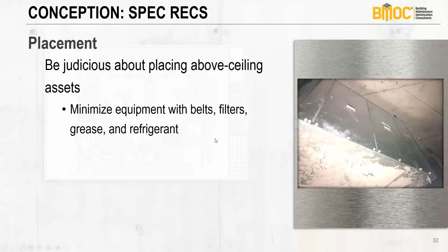Back to above-ceiling equipment: if a unit is above a drop ceiling, install it as close to the ceiling as possible while still allowing access and tile removal. Also consider the usage of the space below and the frequency of required maintenance. The unit in this picture was a particular bugaboo.